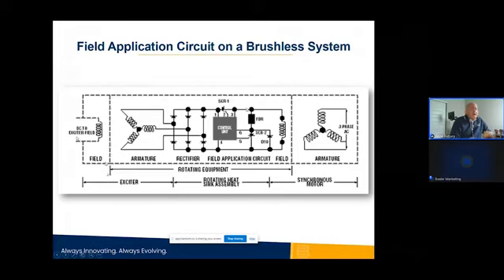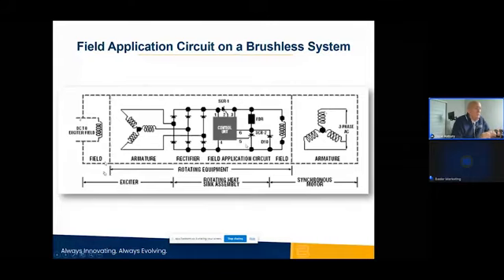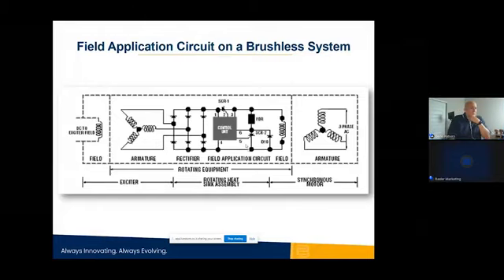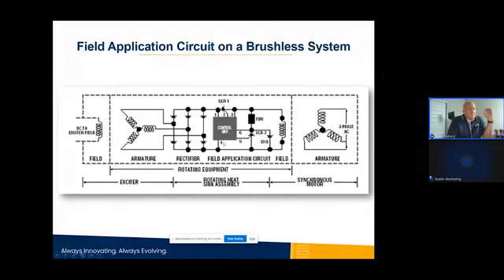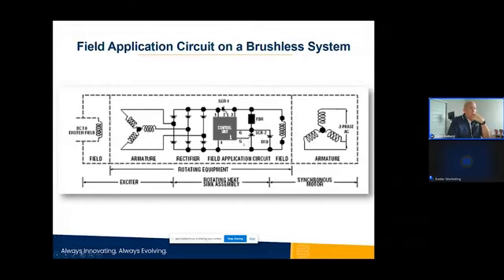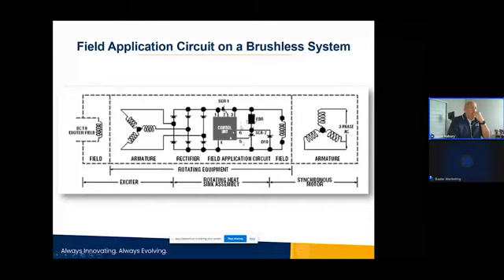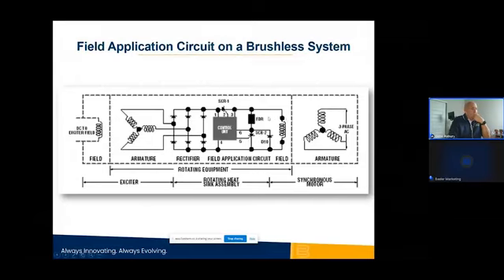You've got a couple SCRs, and keep in mind, this is one way to do it. Different motor manufacturers do it slightly differently, but they'll have some sort of a control unit and some means to apply the field at the right time. So as you can tell, the control unit is monitoring the field discharge resistor, or starting resistor. And once that motor starts to spin, there's an induced AC current across the field discharge resistor that is at synchronous speed.